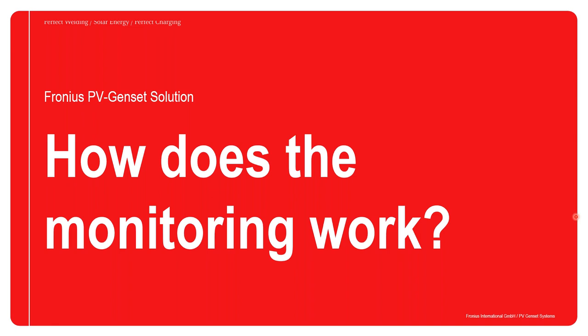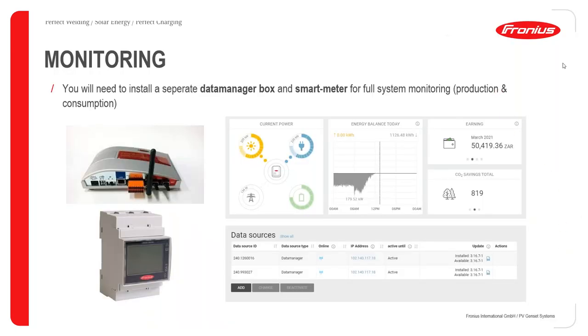For full system monitoring, purchase an additional data manager box and a Fronius smart meter. The data manager box uses its own 12V DC power supply and connects to the Fronius smart meter over Modbus RTU. On SolarWeb, you will have two data managers: one for inverters communicating with the PV controller, and one for the data manager box communicating with the smart meter. Combining these two on SolarWeb gives a full analysis of production and consumption — showing what the grid or genset is producing, what the PV is producing, and what the load is consuming.